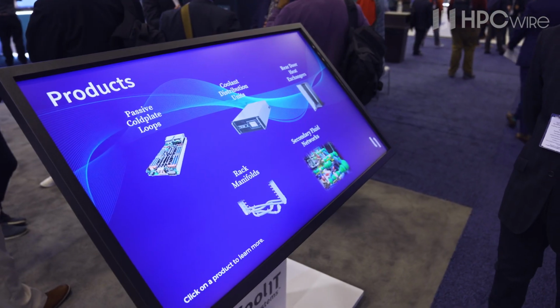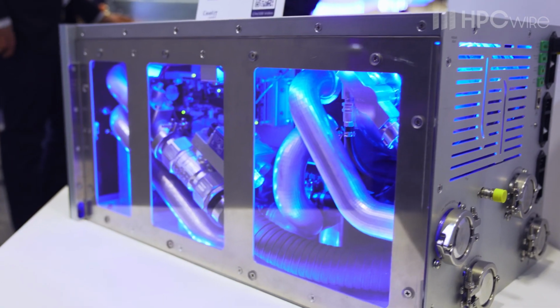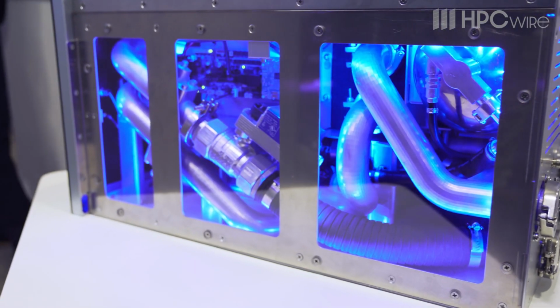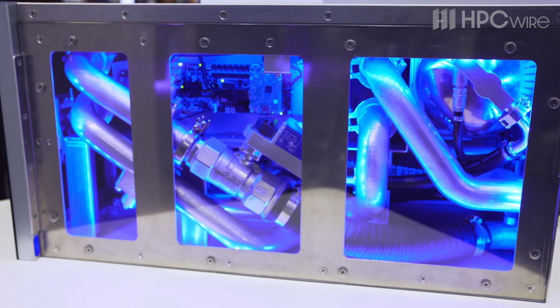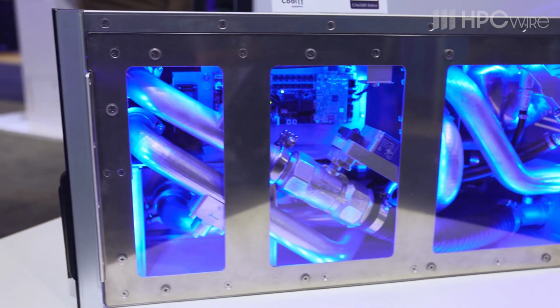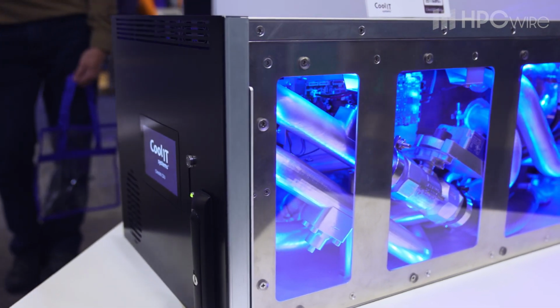This year at our booth we're very excited about our CHX500 coolant distribution unit. We have what we believe is the densest coolant distribution unit on the market - it's a 10U, 500 kilowatts at a 5°C approach temperature. The idea is that you could actually stack 4 of these units in a rack to create a 2 megawatt CDU, or a 1.5 megawatt CDU with redundancy.